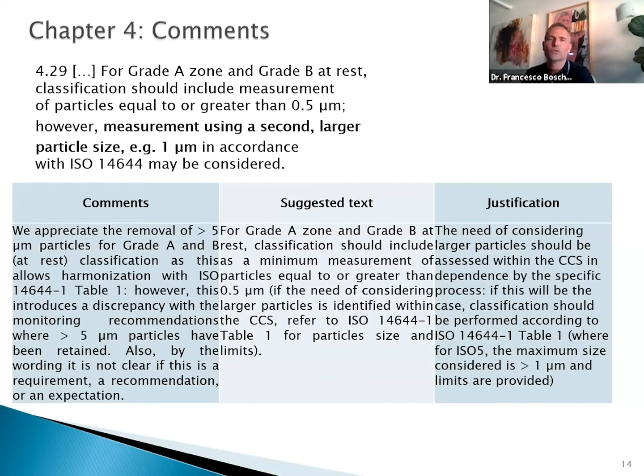What we think is that the need of considering larger particles should be assessed within the contamination control strategy, considering the specific process and the specific facility. And if considering larger particles is needed, we recommend referring to the ISO 14644 table, where we have all the limits and all the sizes which need to be considered. So the rewording is: for grade A zone and grade B at rest, classification should include as a minimum the 0.5. If the need of considering larger particles is identified within the contamination control strategy, refer to ISO 14644-1 table 1 for particle size and limit. So this is the rewording that we suggested. Let's see if it will be captured or not.